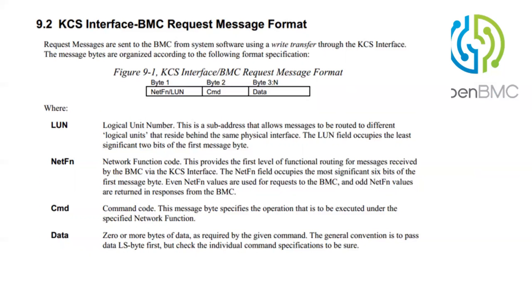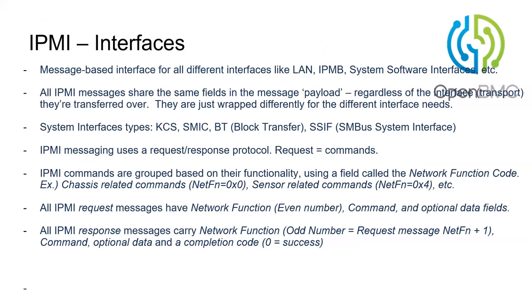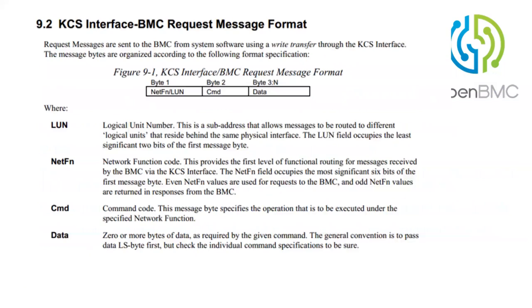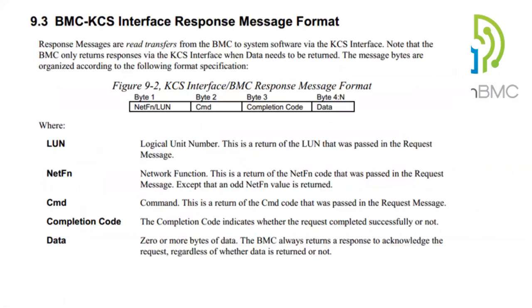An example request format: LUN (Logical Unit Number) uses 2 of 8 bits — usually 00 to denote the BMC, though 01, 10, or 11 can denote other logical entities residing in the BMC. NetFn identifies the group a command belongs to, the command ID is specified, and data is passed (some commands require no data). The response message format mirrors this structure with the same NetFn/LUN and command fields.